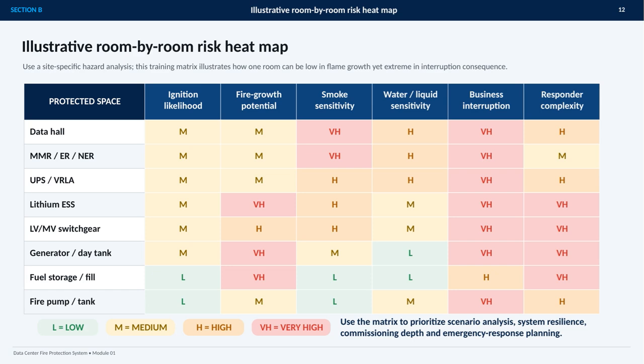The ratings range from low to very high, using the abbreviations shown at the bottom. For example, the data hall is rated very high for interruption consequence, while lithium ESS and several electrical areas show very high ratings in multiple categories. These ratings are illustrative, not a substitute for engineering judgment. We should use a site-specific hazard analysis to validate them, then apply the results to scenario analysis, resilience decisions, commissioning depth, and emergency response planning.